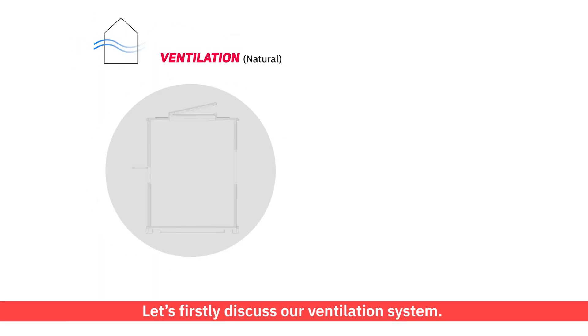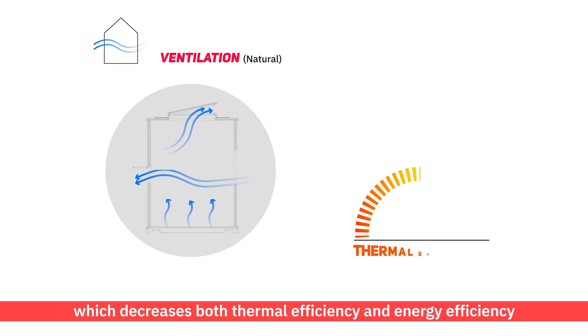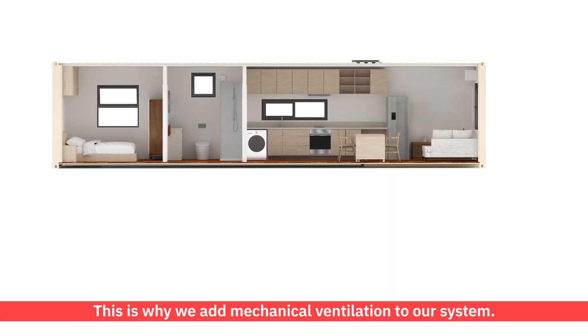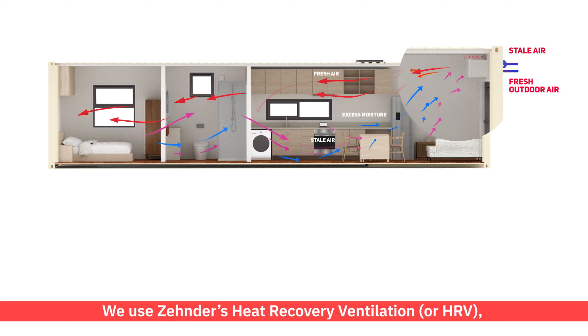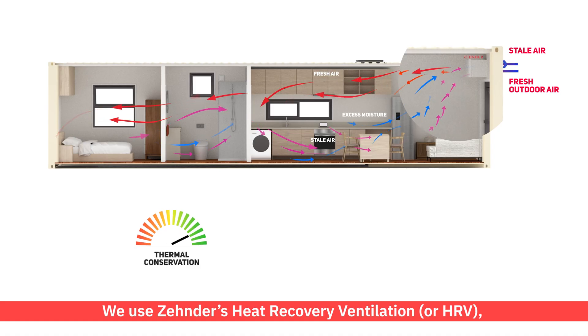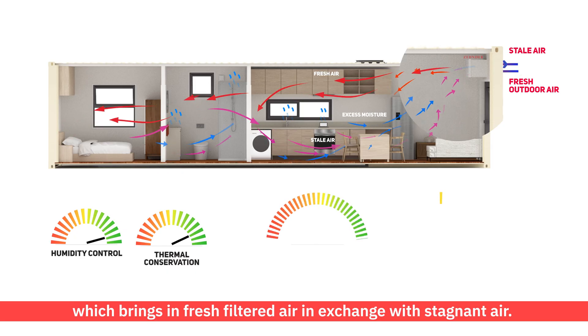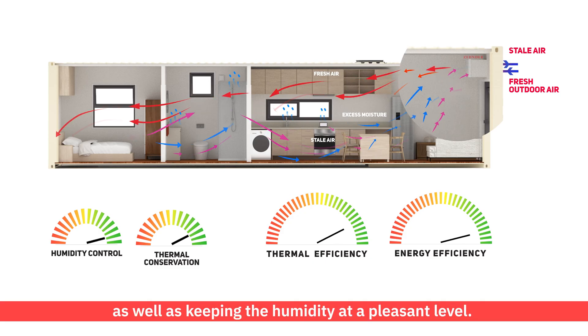Let's firstly discuss our ventilation system. Because containers are more airtight than conventional homes, they need to rely on natural ventilation through windows and doors for air exchange, which decreases both thermal efficiency and energy efficiency. This is why we add mechanical ventilation to our system. We use Zehnder's Heat Recovery Ventilation, or HRV, which brings in fresh filtered air in exchange with stagnant air. Thermal energy is exchanged within the unit to ensure the internal temperature remains constant, as well as keeping the humidity at a pleasant level.